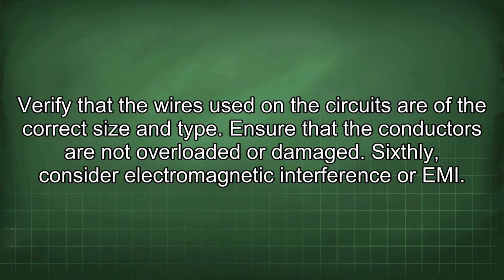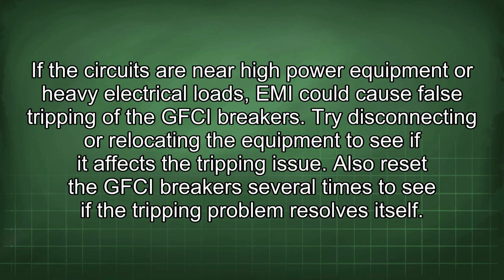Sixthly, consider electromagnetic interference, or EMI. If the circuits are near high power equipment or heavy electrical loads, EMI could cause false tripping of the GFCI breakers. Try disconnecting or relocating the equipment to see if it affects the tripping issue.